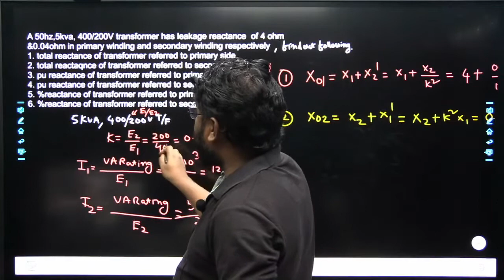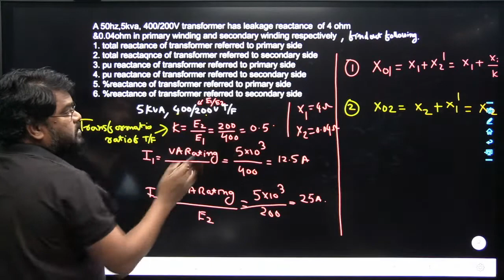What is the formula here? Total reactance of the transformer referred to the primary side, X01, is the existing reactance X1 plus X2 dash, that is X1 plus X2 by K square. X1 is given as 4 ohms and X2 is 0.04 ohms. Substituting, X01 is equal to 4 plus 0.04 divided by 0.5 square, which is equal to 4.16 ohms.